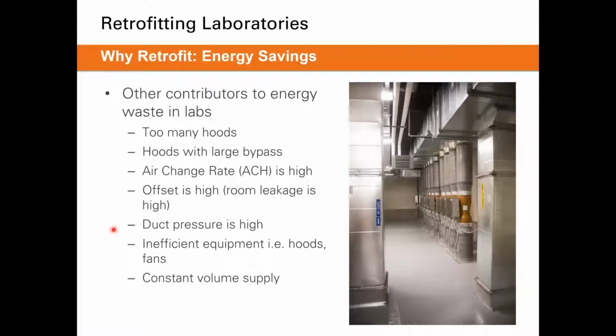If your duct pressure is too high, that would also inflate these energy costs, and that is one that you could go in and try to see if you could reduce without having to replace any mechanical assemblies. The thing you want to be careful with here is that venturi valves specifically require a certain pressure range in order to operate and maintain their flow accuracy. So if you're turning down the duct pressure, just ensure that all of your equipment is still within its operating pressure range.